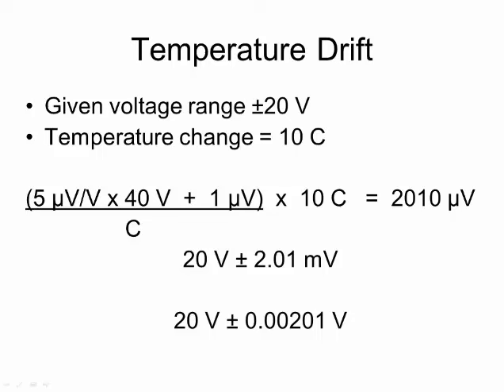We can calculate the expected temperature drift by multiplying the voltage range — 40 volts — times 5 parts per million (i.e., 5 divided by 1 million), adding 1 microvolt, and multiplying the product by the temperature change of 10 degrees Celsius. The result is 2010 microvolts, which is the same as 2.01 millivolts. So at full scale, the temperature drift would be expected to produce an uncertainty of plus or minus 2 millivolts.